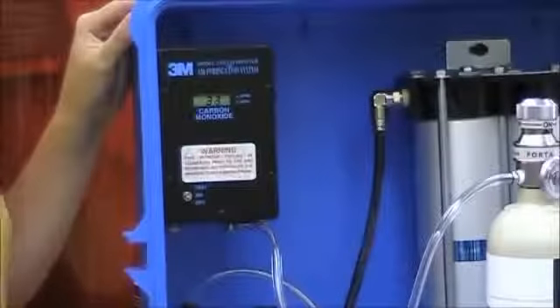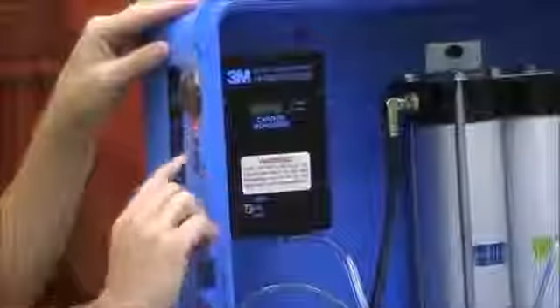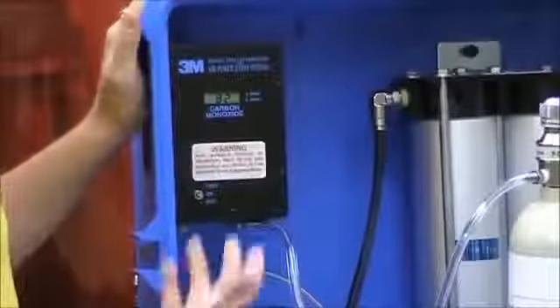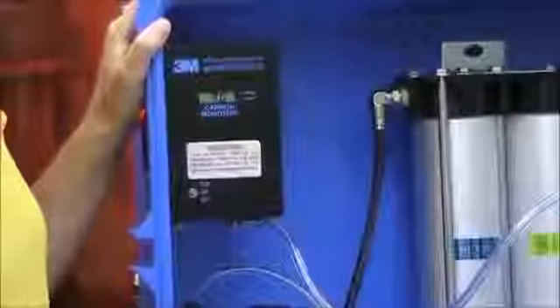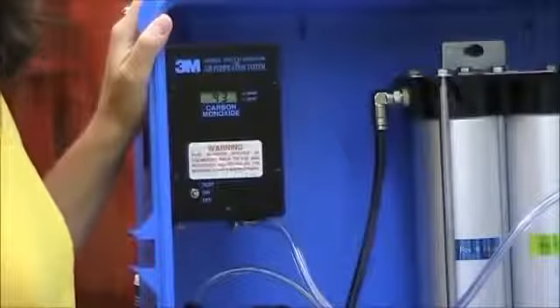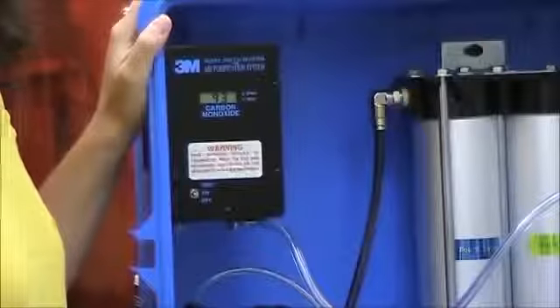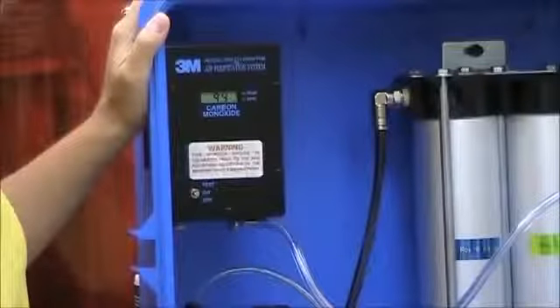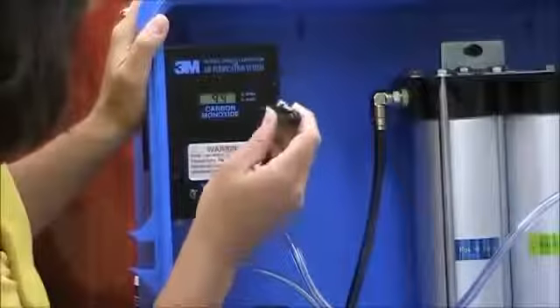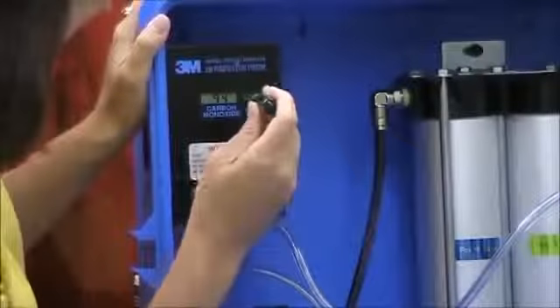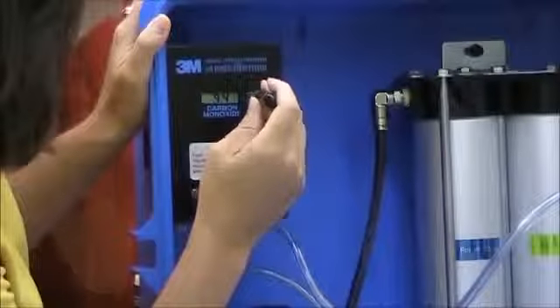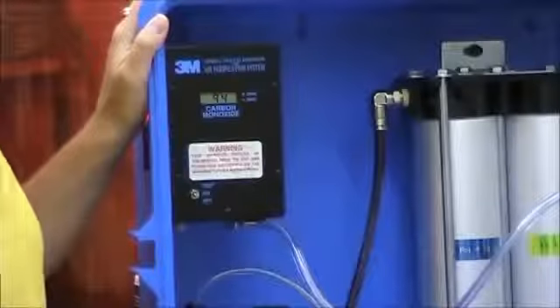So there it goes. When it hit 10, I could hear and then see the red alarm light on this side of the panel. And it goes up rather quickly. I'm already at 83 parts per million. And I'll adjust it if necessary. You just want to give it a little bit of time to make sure it's able to stabilize before you do any adjusting. I'm at 94 parts per million. I'm just going to adjust it by giving it just a slight turn. So it's at the 95 parts per million.